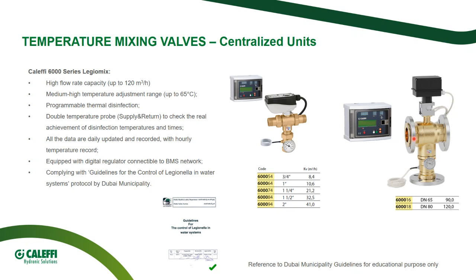So they have two probes, one for the supply and one to be installed on the return of the recirculation pipe. All the data are updated daily and recorded, and once an hour the temperatures are recorded. They are equipped with a digital programmable regulator that in the latest version can be connected to the BMS network, Modbus or BACnet. This kind of solution complies with the guidelines for control of Legionella in water system protocols, also the version by Dubai Municipality.